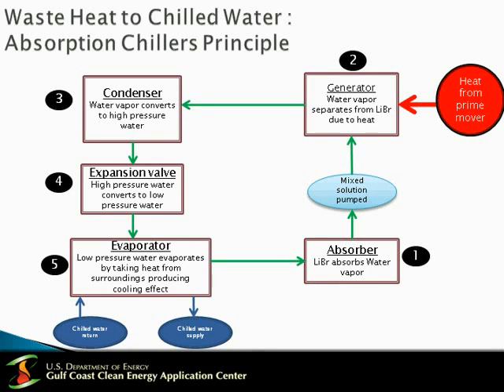Heat, the water vapor separates from the lithium bromide and it goes to state 3, which is the condenser. Now in the condenser, the water vapor converts to high pressure water. Then it goes to state 4, where the water is diverted to an orifice or an expansion valve, which basically converts the high pressure water to low pressure water.